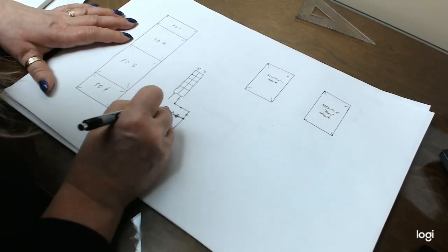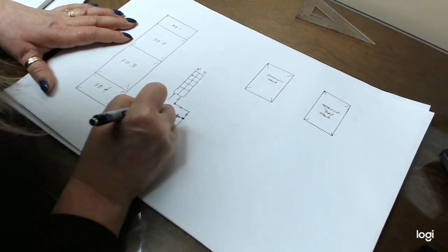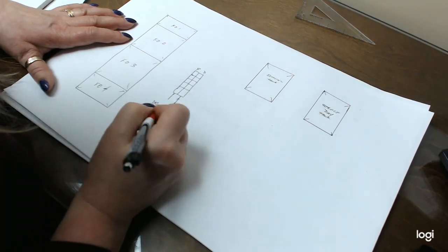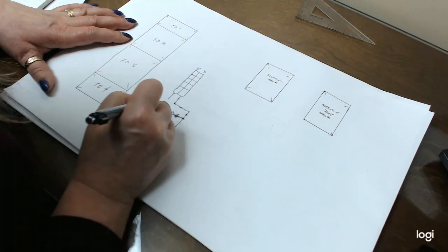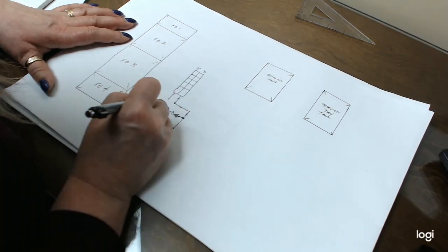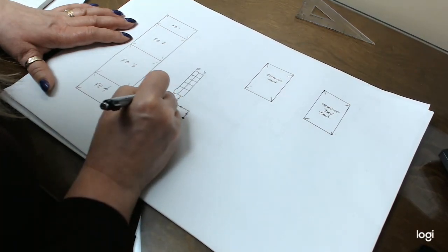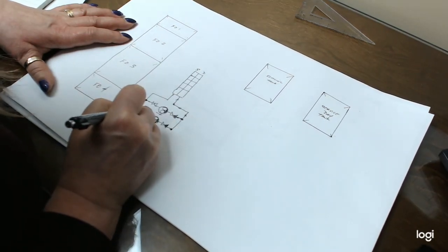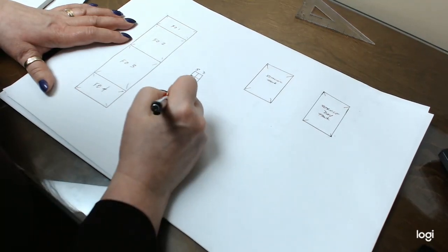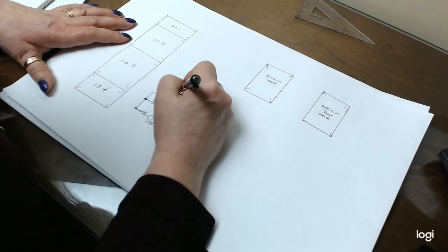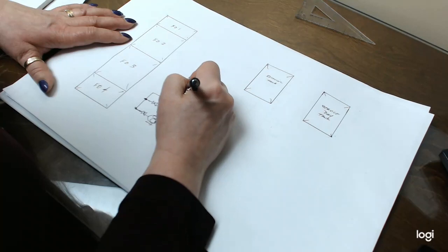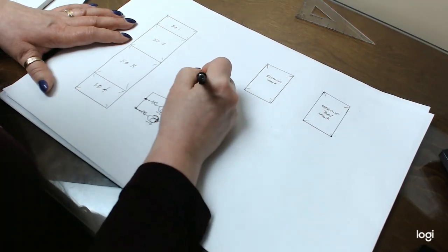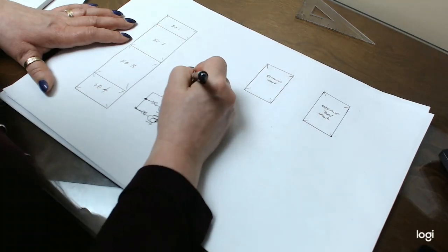On this side of the pump, I'm going to put in a gate valve. Okay, so this would be an isolation valve so that I can isolate the pump and do repair on it. So once again, I'm just going to connect it all in here, like so, and I'm just putting these dots in here so you can see that these are junction areas, okay? All right, so your manifold typically has the X's in it to depict that these are gate valves, so they're either totally open or totally closed.